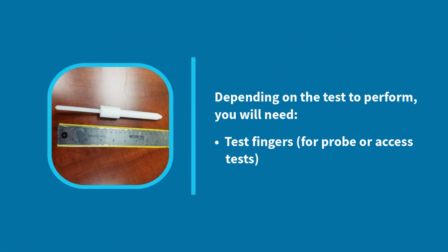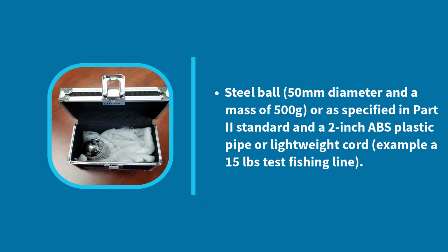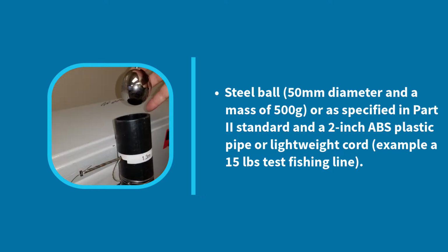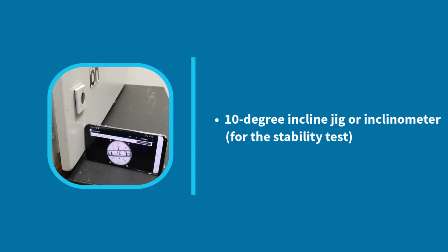Test apparatus. Depending on the test to perform, you will need test fingers for probe or access tests, a steel ball, 50 millimeters diameter and a mass of 500 grams, or as specified in Part 2 standard, and a 2-inch ABS plastic pipe or lightweight cord, for example, a 15-pound test fishing line. A 10-degree incline jig or inclinometer is needed for the stability test.